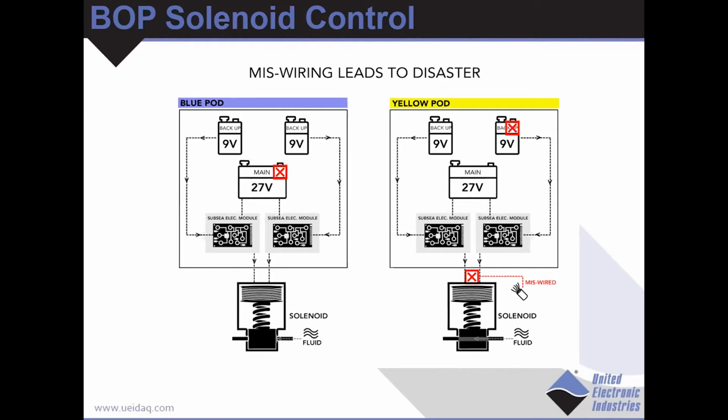So the operator had no idea of these conditions. There was no diagnostics and no checks to ensure they were wired properly. If we take a look at those subsea electric modules, we'll see they're basically just switches. So there's no extra information that can be gathered.